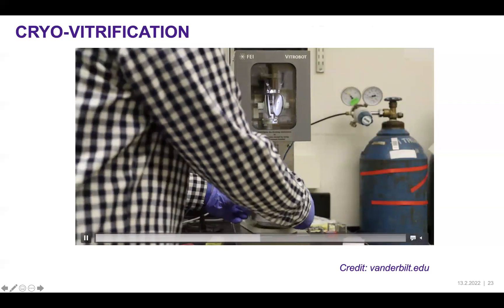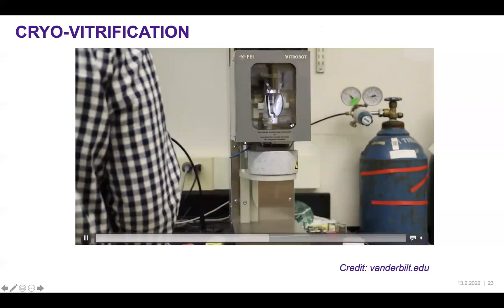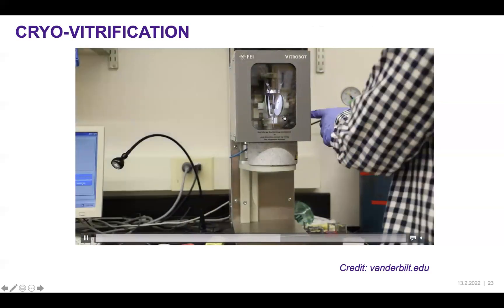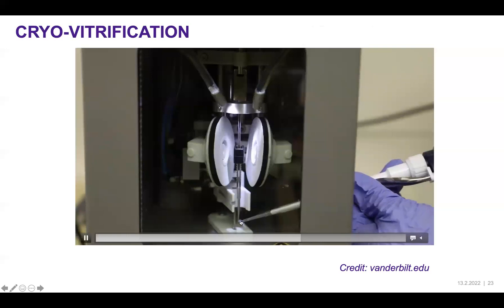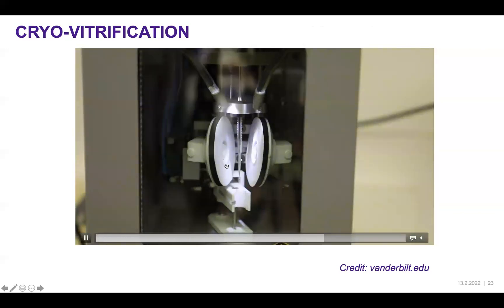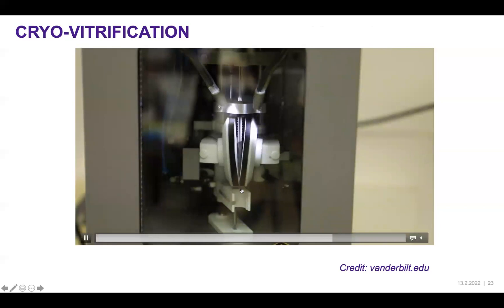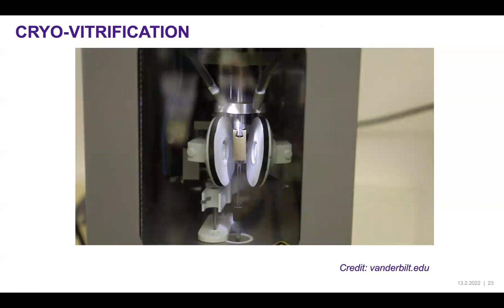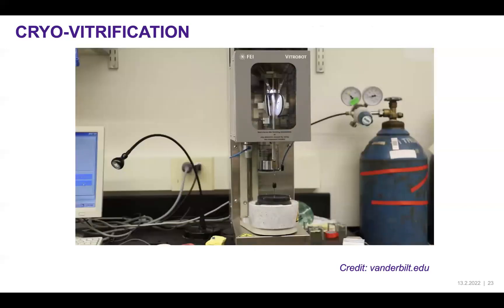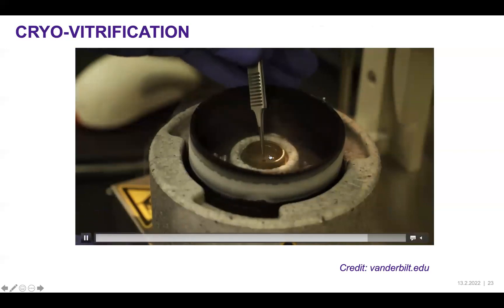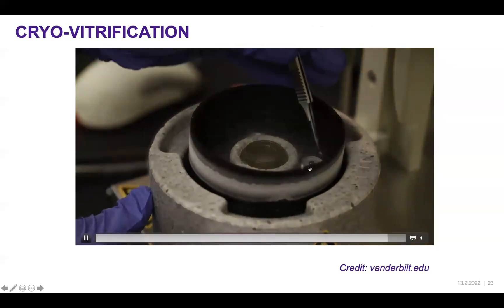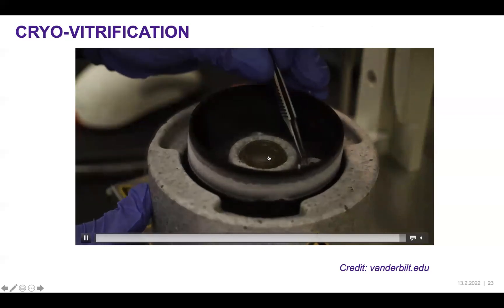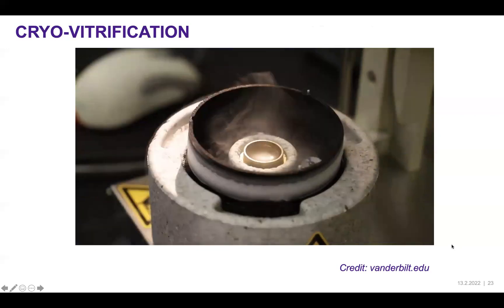You load about two to three microliters of sample to the grid. Everything is controlled by computer and you quickly blot the sample, which leads to a 70 to 100 nanometer thick ice film. You then rapidly plunge it — this entire process is called plunge freezing. The grid is then transferred from liquid propane to liquid nitrogen for storage. Once the amorphous ice is formed it is stable as long as the temperature is maintained.